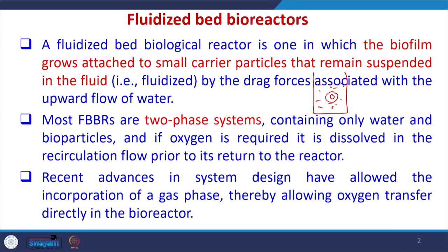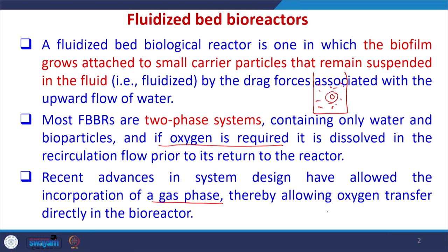Most fluidized bed reactors are two-phase systems — they contain only water and bioparticles — and if oxygen is required it is dissolved in the recirculation flow prior to its return to the reactor. Recent advances in system design have allowed the incorporation of a gas phase as well, thereby allowing oxygen transfer directly in the bioreactor. So with recent advances the system has become a three-phase system, containing not only water and bioparticles but also oxygen or air.